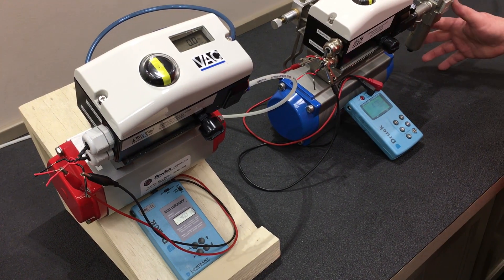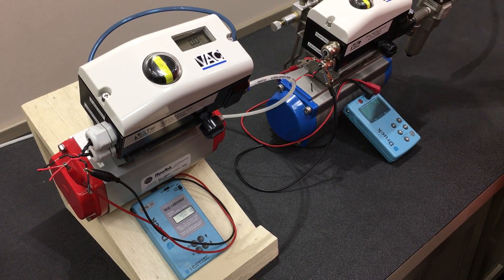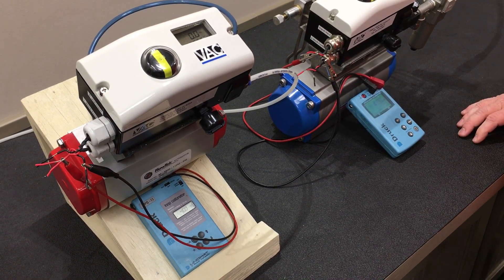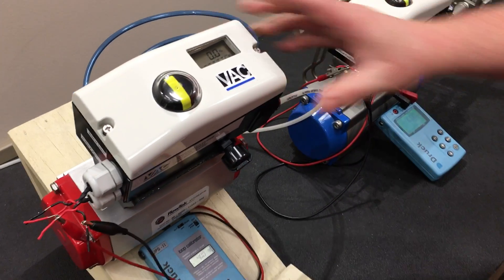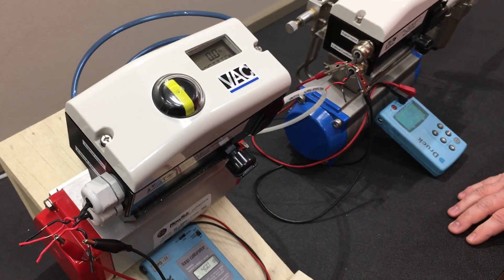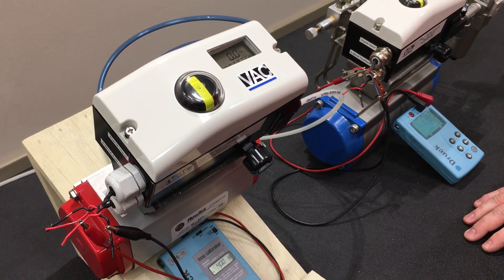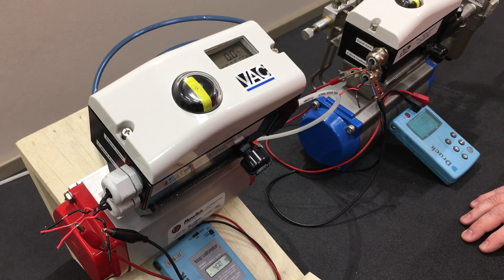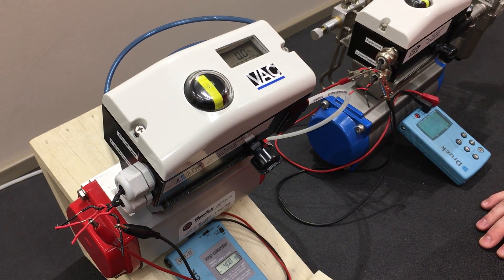This is a demonstration of a positioner with a fail freeze function as well as a pneumatic lockup valve. First, we're going to look at a standard positioner, which is a fail-safe positioner. Whenever it has a signal and the signal is lost, it goes to a zero position, no matter what the error signal was.